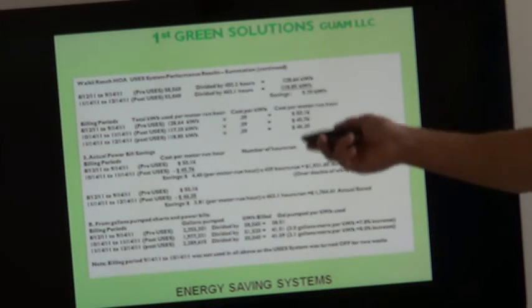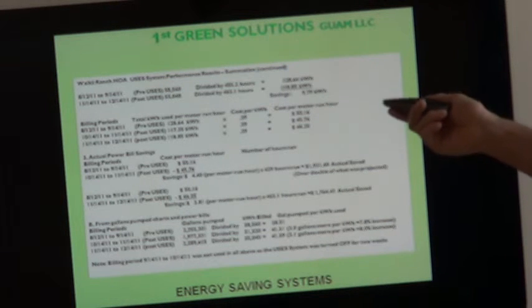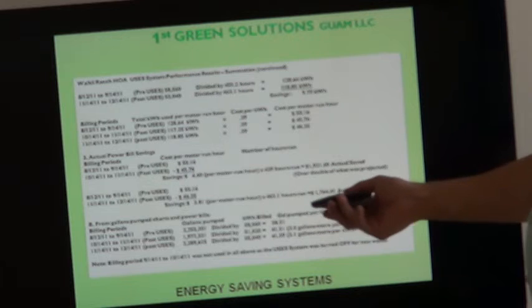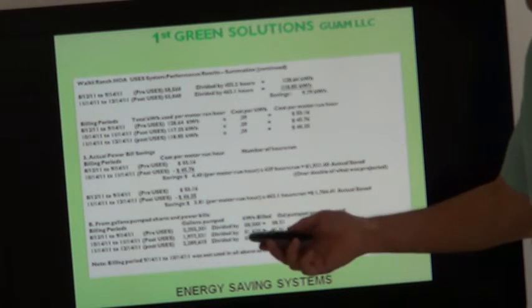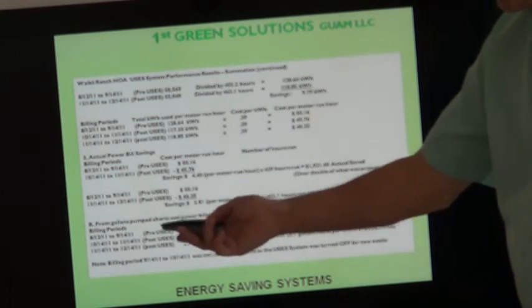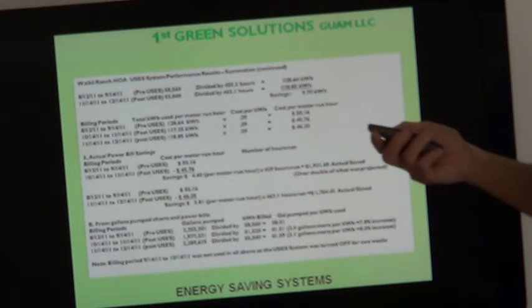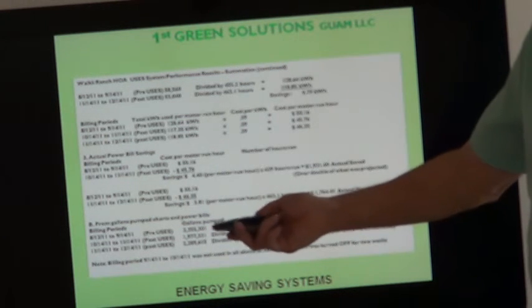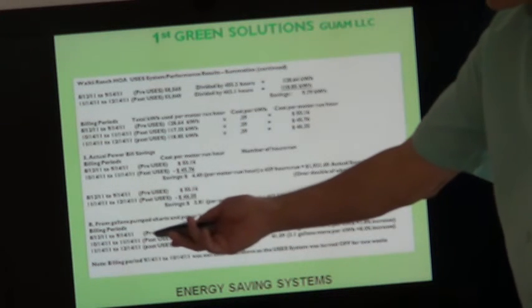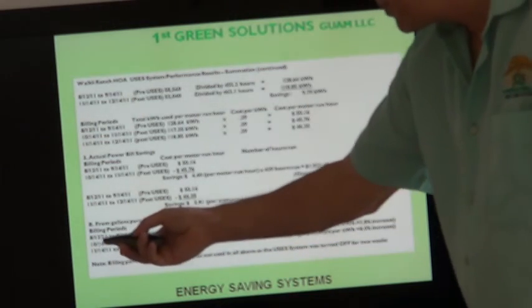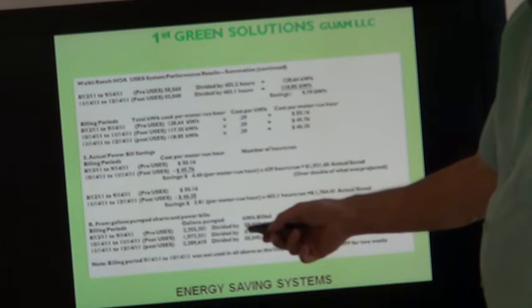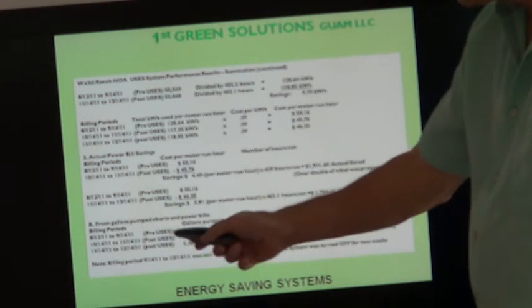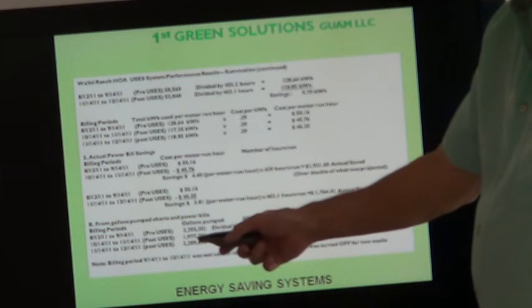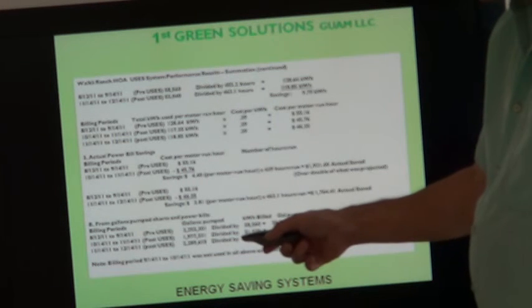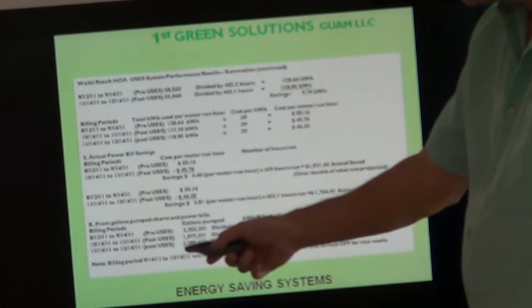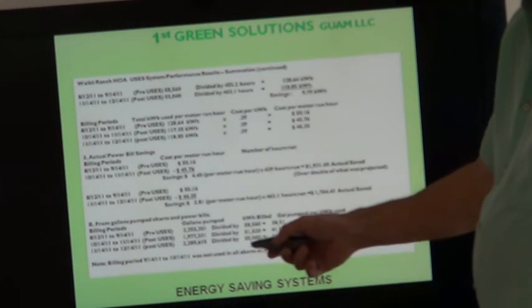The significance of this particular installation is they wanted to know how much they were saving on the gallons that they were pumping. So as a result of the USES installation and the power bills that we were able to acquire, and they also keep graphs and charts on how long the motors are pumping. The overall gallons pumped were 2,255,000 before the USES units went in this month billing period, and they used 58,000 kilowatt hours. The following 2 months after the USES units went in, 1,977,000 gallons were pumped in this month at 51,000 kilowatt hours, and 2,289,000 gallons were pumped at 55,000 kilowatt hours.